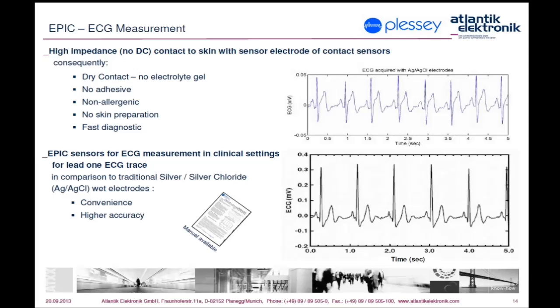In order to show what is possible to achieve with EPIC sensors compared to common silver chloride electrodes, a study was conducted comparing results of those measurements — in this case only lead one of ECG signals. As shown on the graphs on this slide, results taken with EPIC sensors are to some extent better. A more detailed explanation is provided in the relevant application notes issued by Plessey.